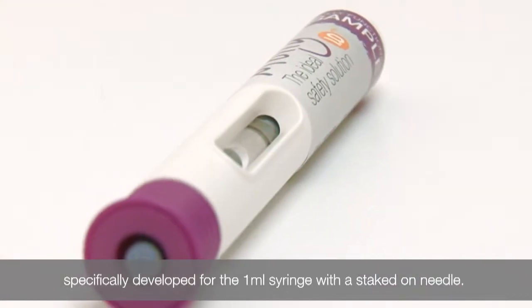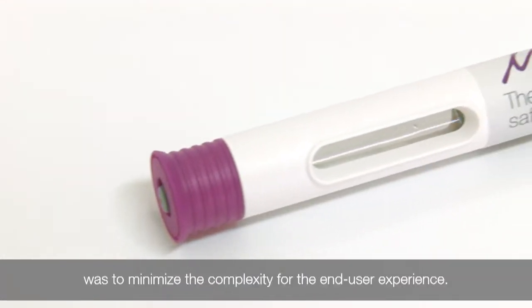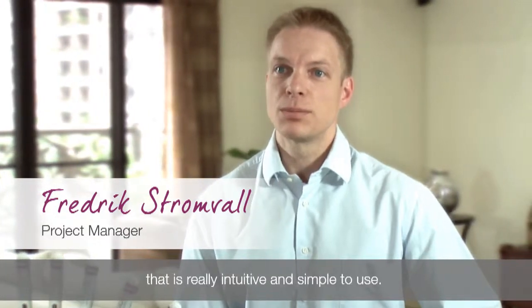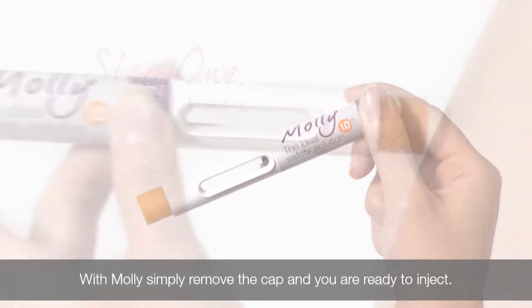Molly is a disposable single-use auto-injector specifically developed for the 1 ml syringe with a staked-on needle. One of our goals with this product was to minimize the complexity for the end-user experience. We have done this by developing a device that is really intuitive and simple to use. With Molly, you simply remove the cap and you're ready to inject.